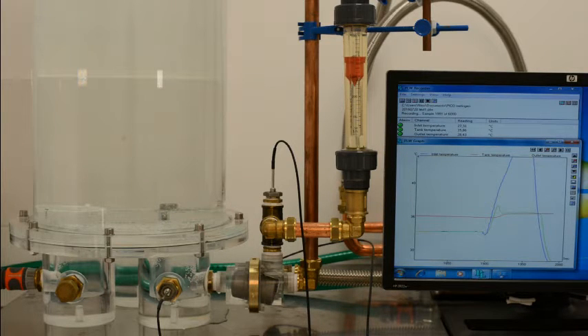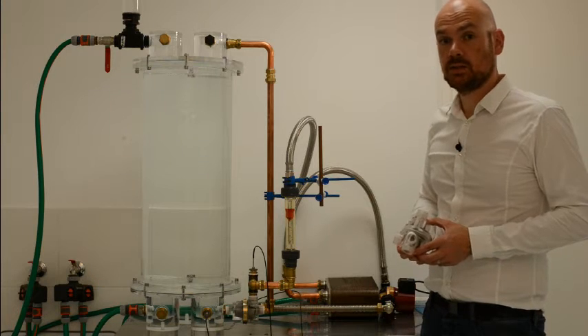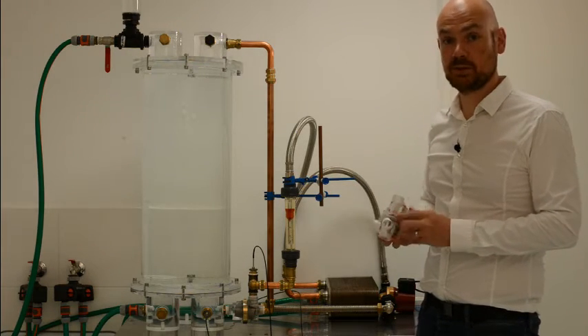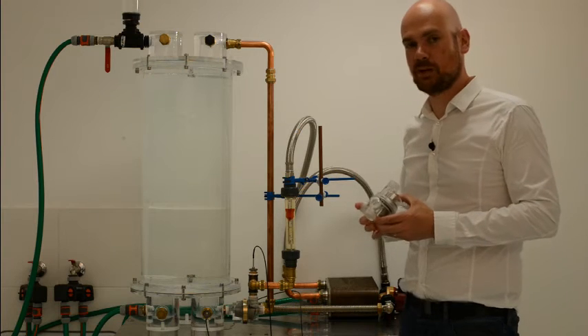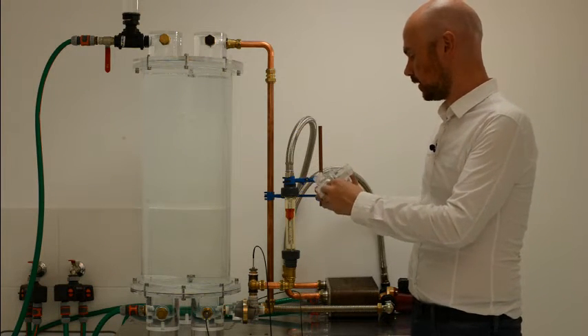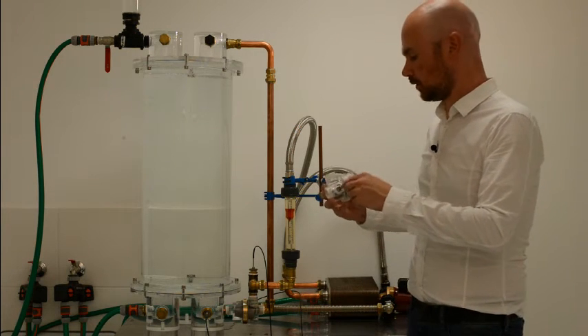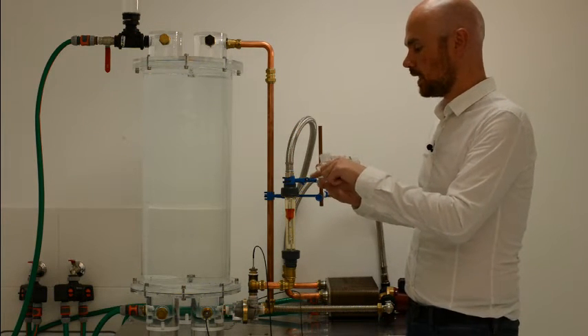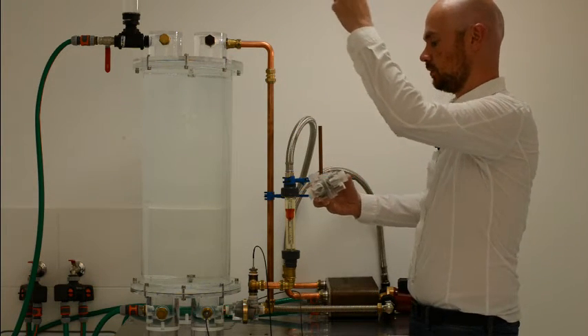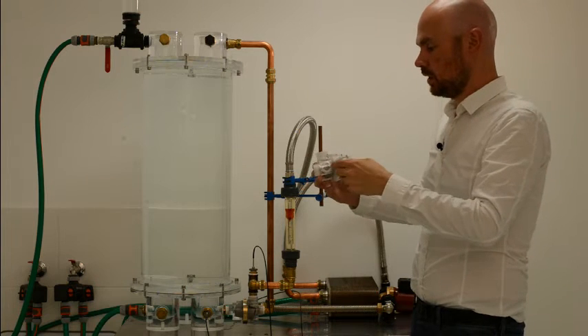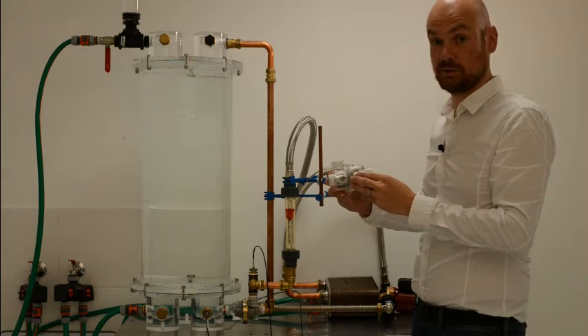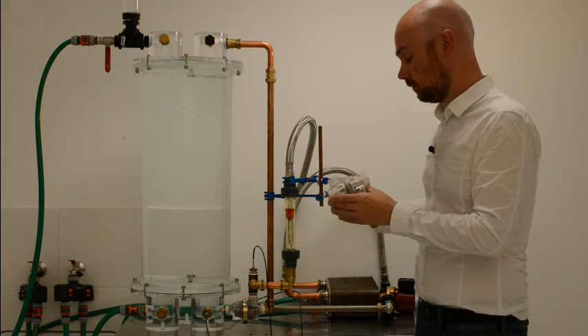So as you see now from this graph, heat initially was bypassed, then it was opened because heat could be delivered to the tank, but as soon as the inflow cooled down again, the tank was bypassed again to avoid heat being withdrawn from the tank. So now to explain how exactly the valve works, here is the valve again. I'll just first go through how it is installed again. So here is the inlet flow into the valve, which is at the back of the installation here. And from that inlet flow, the flow can either go straight back out of the valve, in which case it first passes through the heat exchanger or the buffer tank, and then comes back into the other end of the valve. Or it can go straight into the valve, and in that case the buffer tank or the heat exchanger is bypassed, as you see here as well.